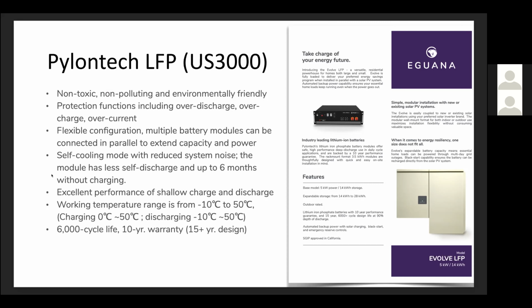The module has less self-discharge or parasitic loads, and up to 6 months without charging is possible. It has excellent performance characteristics of shallow charge and discharge. The working temperature range is important here. It goes from -10 C to 50 C. So from pretty cold to pretty hot. You can do the math. For charging, it's from 0 C to 50 C, and discharging is from -10 C to +50 C. The warranty is based on a 6,000 full cycle life or 10-year warranty with an anticipated 15+ year design. And this is what it looks like when installed.